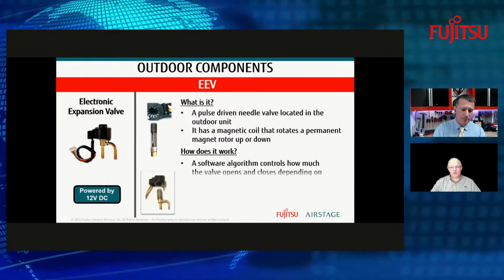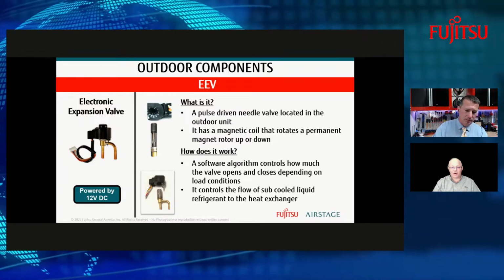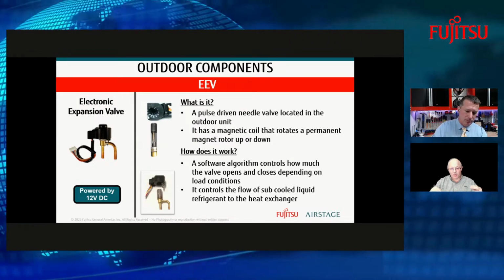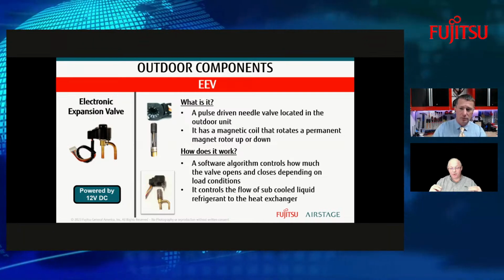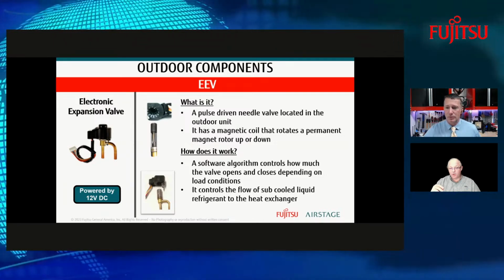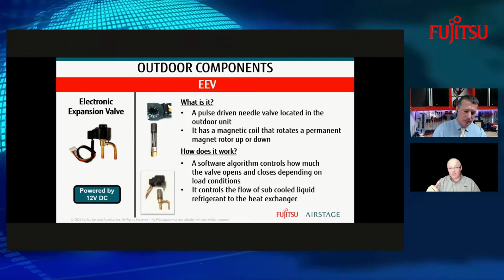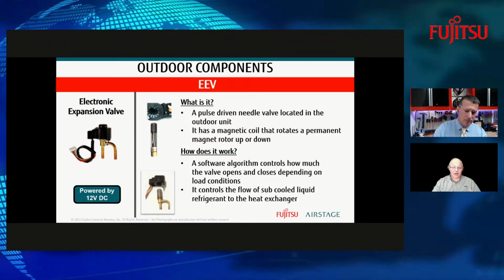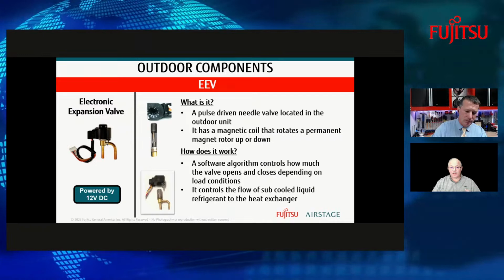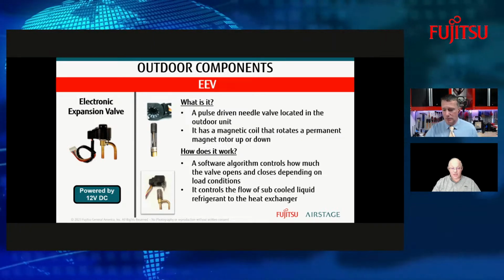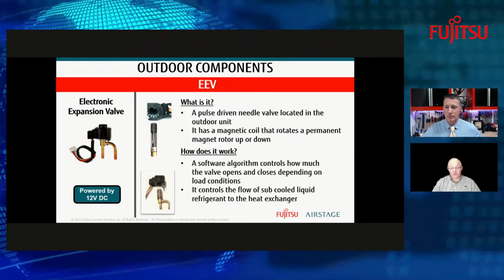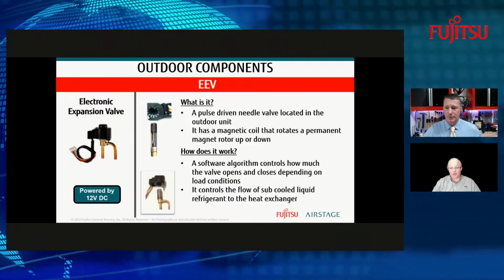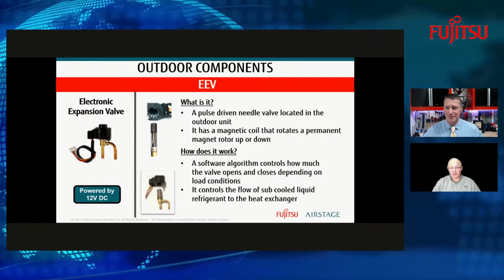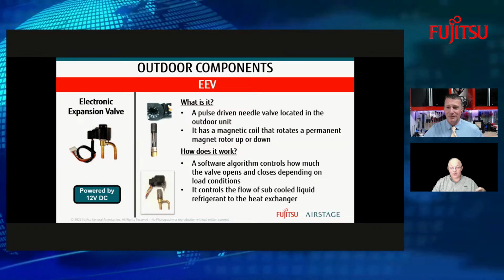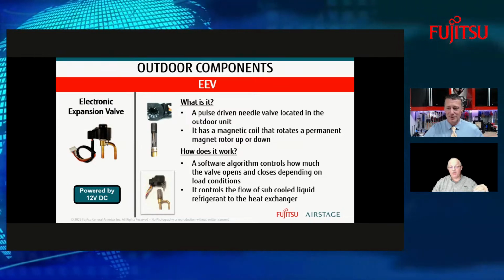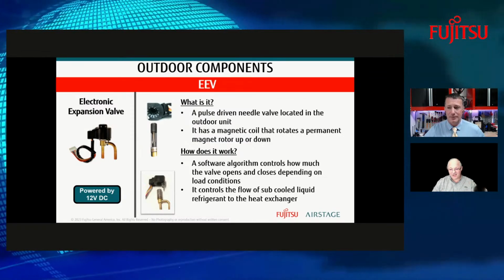So how does it work? Well, it has a software algorithm that controls the opening and closing of it. Depending upon what the load conditions are will depend upon what that EEV is going to do. The EEV is not going to make any changes until the system tells the compressor and the fan motor it's time to speed up a little bit. Once it does that, if it says we need more load, then it knows exactly, through the software algorithm, to tell that EEV, you need to open up to this level, this many steps, and then stop.